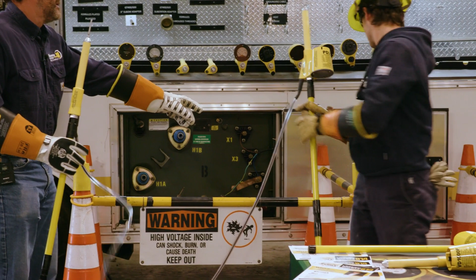So what we've done is we're making an accessory change off the cone tip. If you're making a tool change, equipment change, accessory change, what we're doing is disengaging from that energized field. We're walking a few steps away and making the change there. It takes a little longer in your day to get the job done, but it's a lot safer. It's intentional. Safety has to be in your consciousness. It has to be intentional. You've got to create that, you've got to do that.